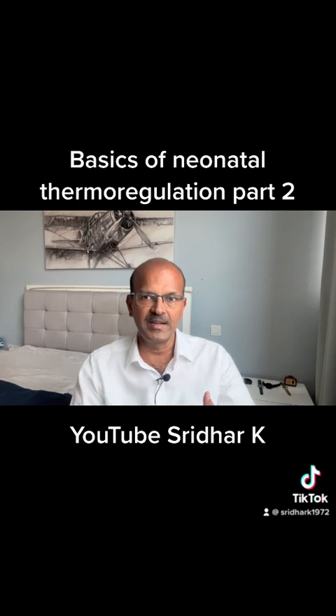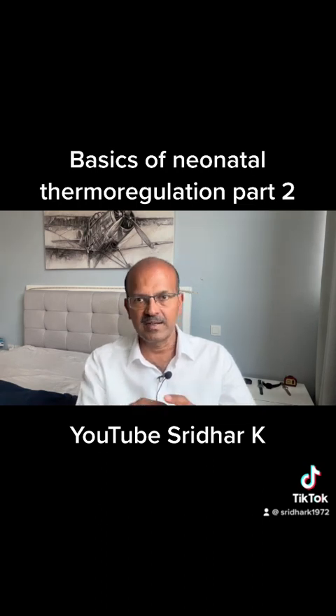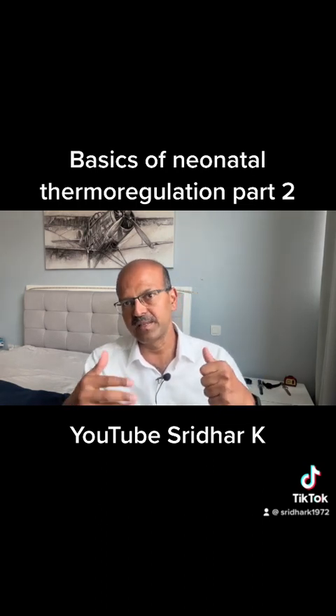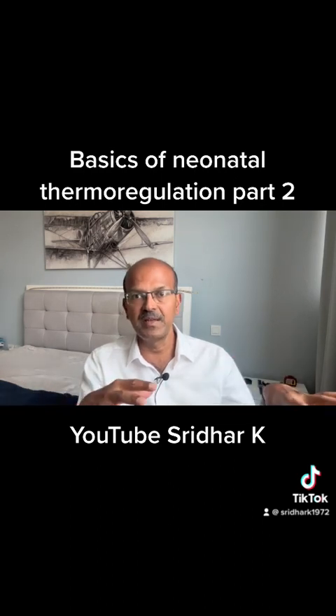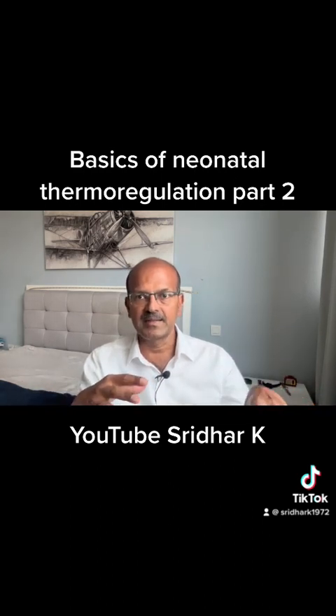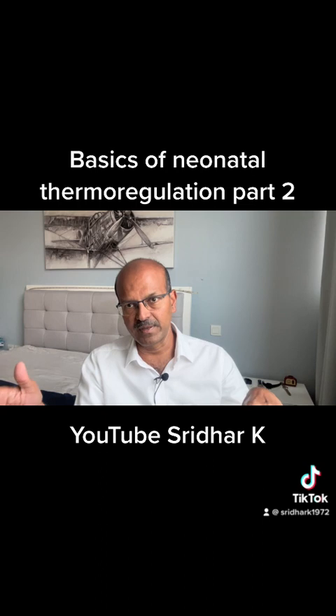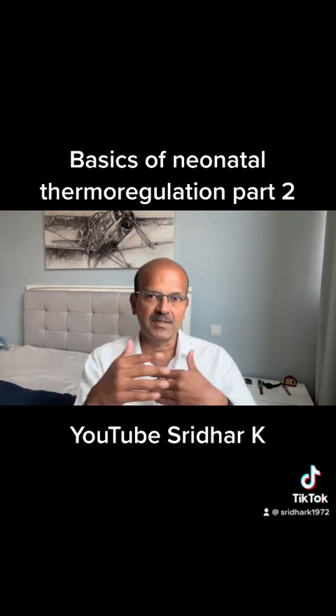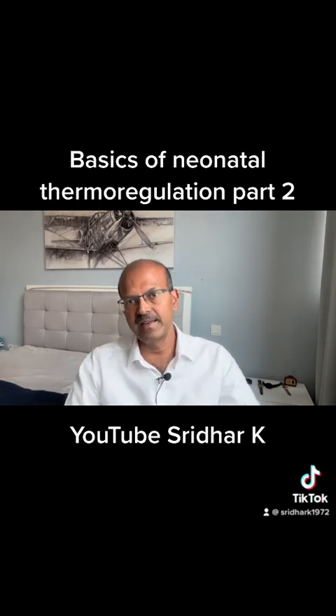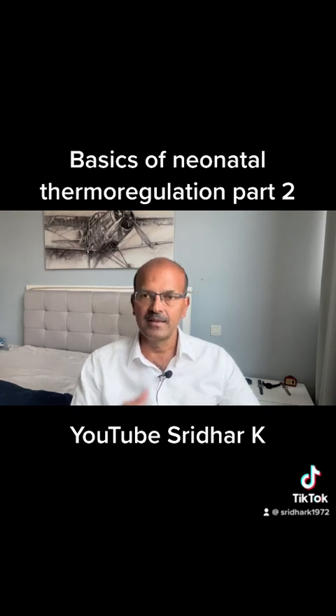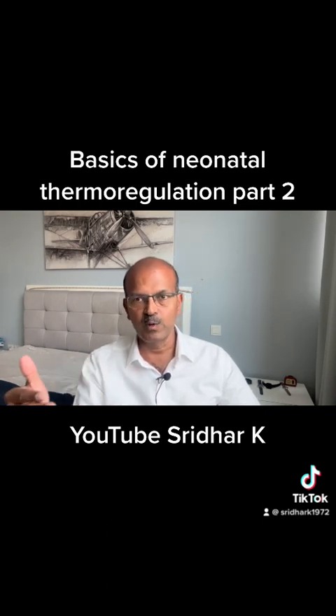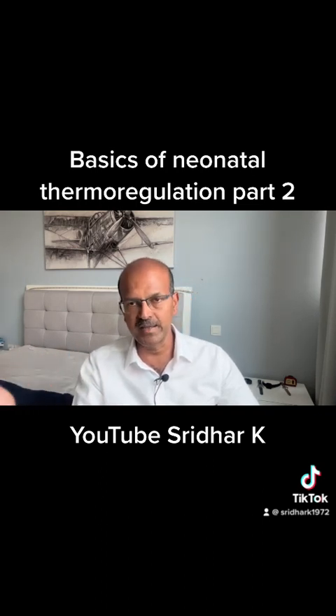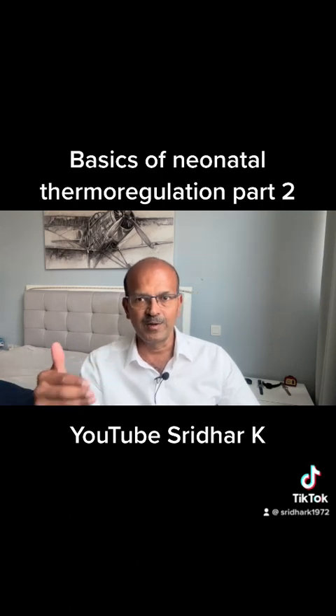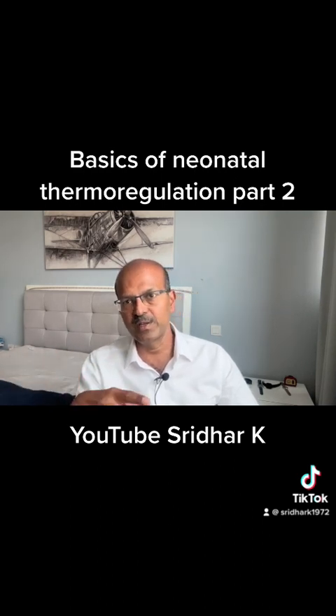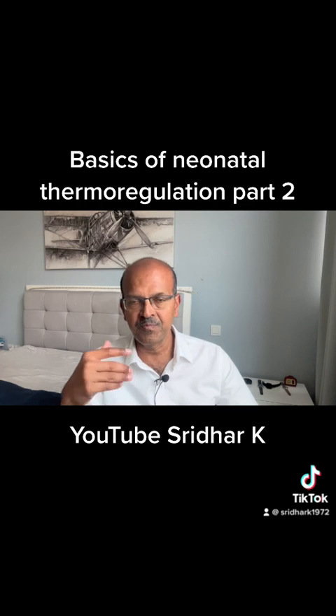So the relative humidity, which is actual water vapor content in the immediate area surrounding the baby, is increased, and so the baby maintains the temperature without losing heat from evaporation. So evaporation happens according to the gradient. If the gradient in your environment is high, they lose heat, they lose water vapor, and evaporation produces cooling. And so if this keeps going on, you cannot maintain the baby's temperature. That's why you need humidification for a small baby.